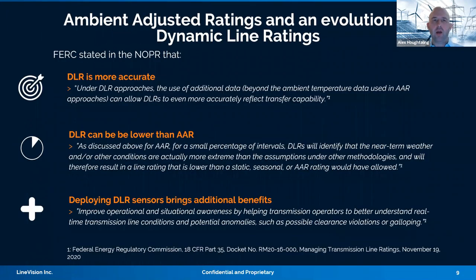Some of my thoughts on the importance of this and the distinctions between ambient adjusted ratings and dynamic line ratings. Rob will get into that shortly, but at a high level, if you read the NOPR itself, you'll see quite a few mentions of dynamic line ratings, and DLR is shown to be more accurate. So it's my opinion that the stepwise approach we're seeing from FERC with ambient adjusted ratings is leading us to a place where we'll arrive at the ability to have dynamic line ratings incorporated into the grid. We'll get into the technical distinctions between those terms in a moment.